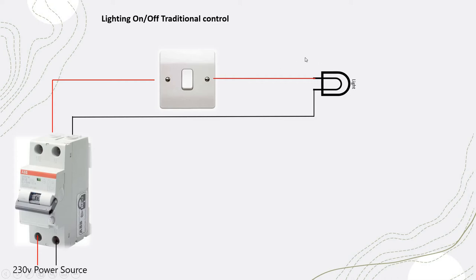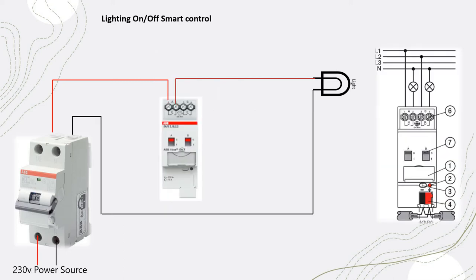If the switch is two-gang, you don't need to pull the live wire again from the DB to the switch — it's only wired internally and you can pull the live cable directly to the light, looping the neutral between lights. One light circuit can have multiple lights connected together, with the final wire coming from the switch. For example, in a bedroom with spotlights, cove lights, and a chandelier, you'd have a three-gang switch with one live cable from the DB distributed to different light types.